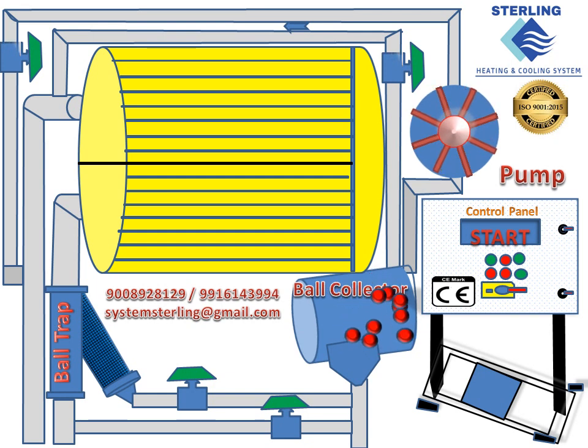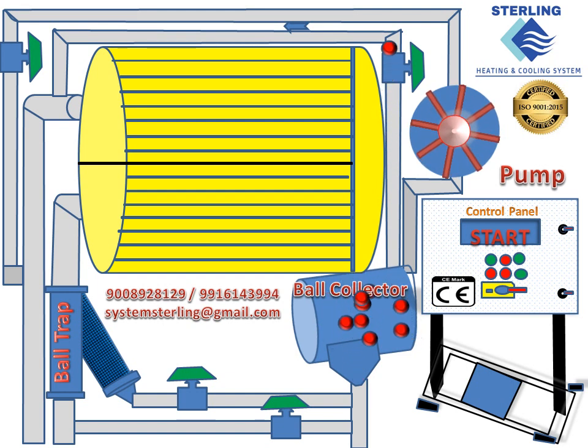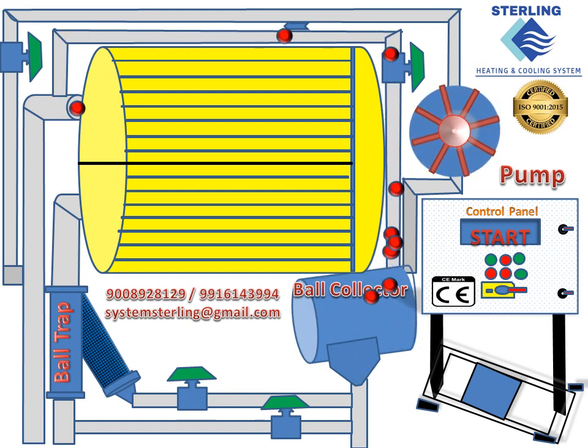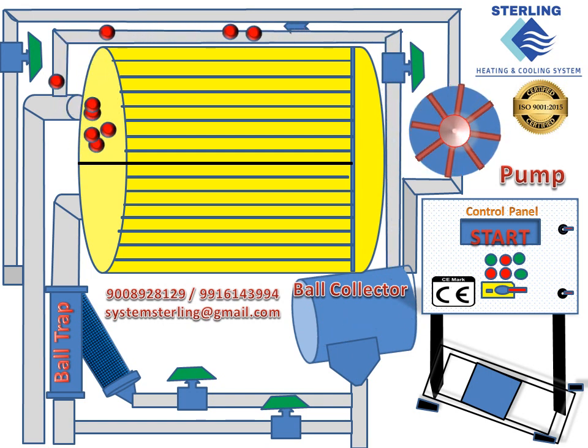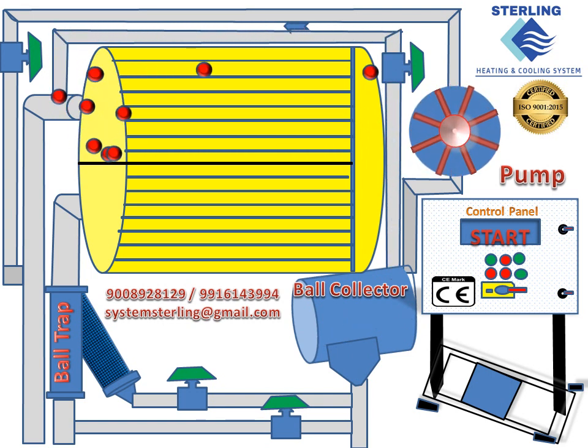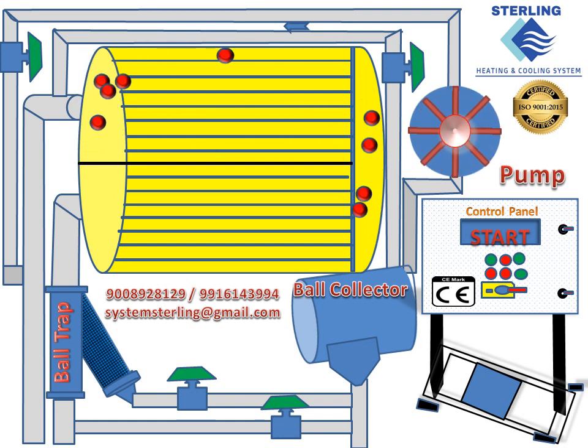The balls move inside the copper tubes to scrub the inner wall of the tube. After leaving the tube, the balls exit the end cover of the condenser with the circulating cooling water and enter the ball collector installed on the outlet pipeline. The ball trap in the ball collector then traps the balls, with the water flowing away through the screen. The balls then return to the ball injector, completing a whole cleaning process.